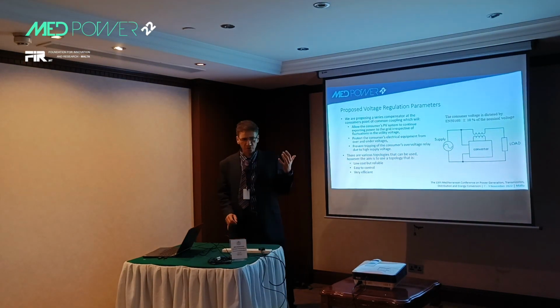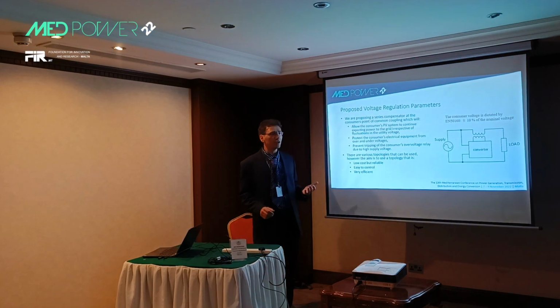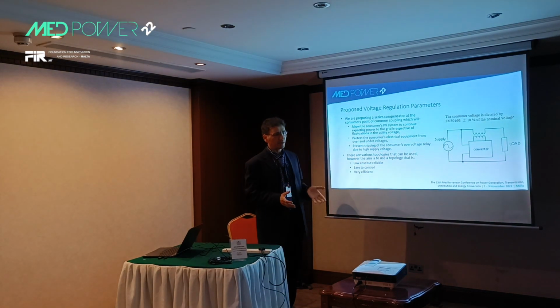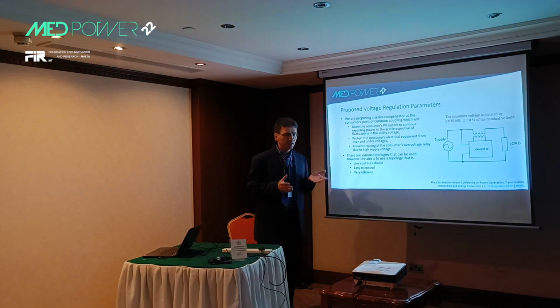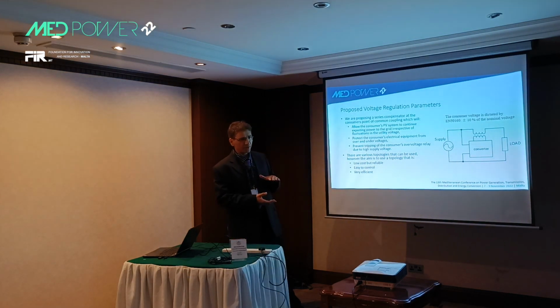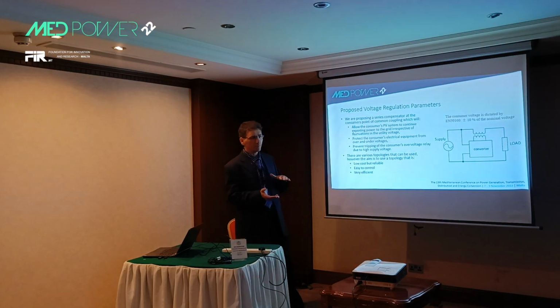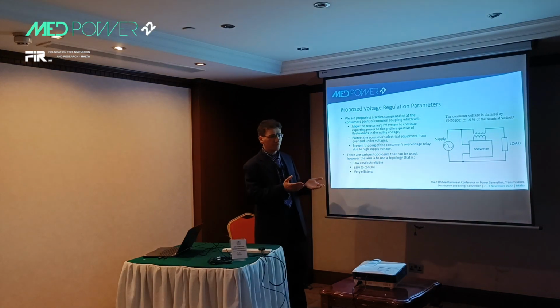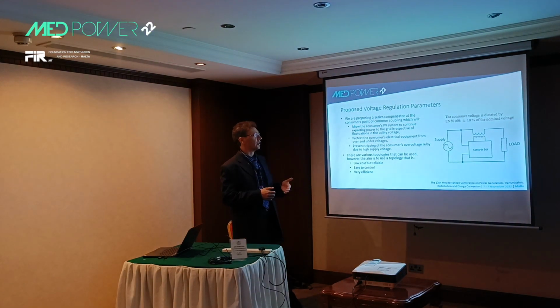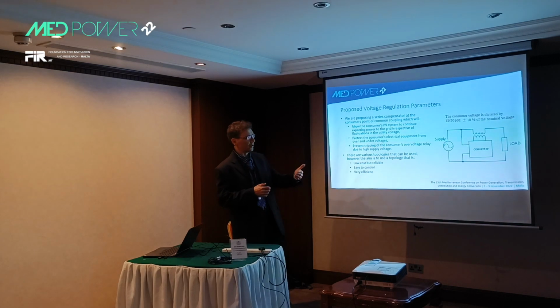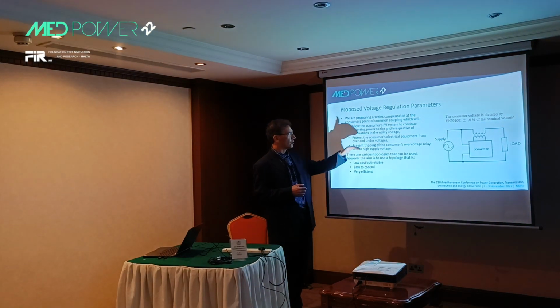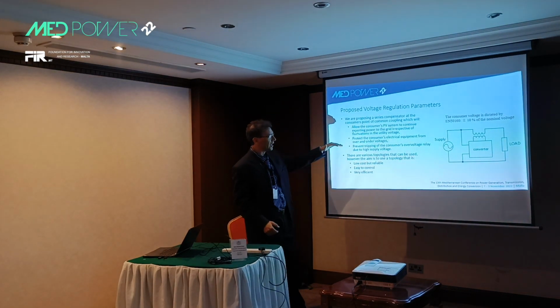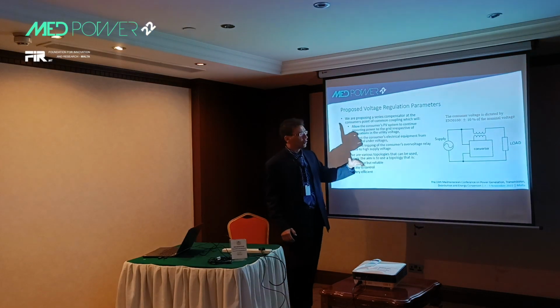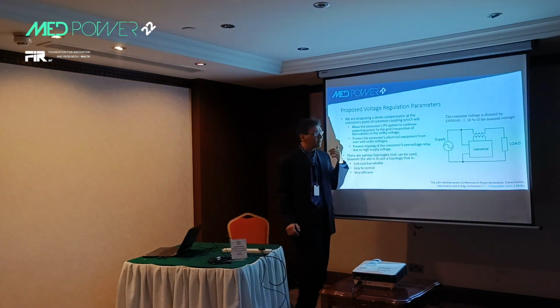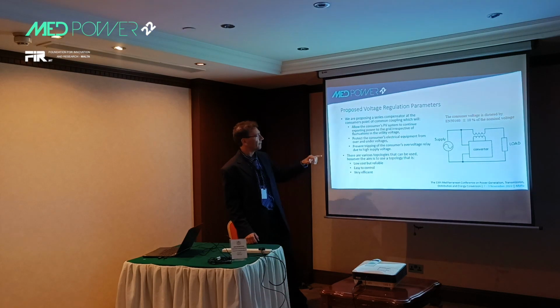Why am I saying it will continue exporting power? Because if all the systems generate at the same time and the voltage goes up on the lines, the protection system of the inverter will see an overvoltage and will basically disconnect the inverter from the grid. And like that you lose renewable energy generated into the grid. So our circuit is going to allow the PV system to continue to generate into the grid even though the supply voltage is very high.